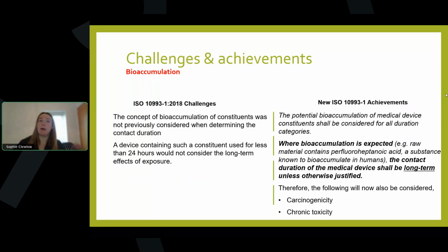You're early on in your biological evaluation process. So this categorization is based on information you have available to you from the raw materials. That means from that information you've got on your raw materials, if you've got something that may be bioaccumulative, you're then considering additional relevant effects. So just bear in mind this change doesn't mandate extractable and leachable testing, but if you then go on to do extractable and leachable testing, because you need to obviously do so for gap analysis purposes, and then you find something that might be bioaccumulative, you then might have to return back to that categorization stage, recategorize and consider if there are any other relevant biological effects.